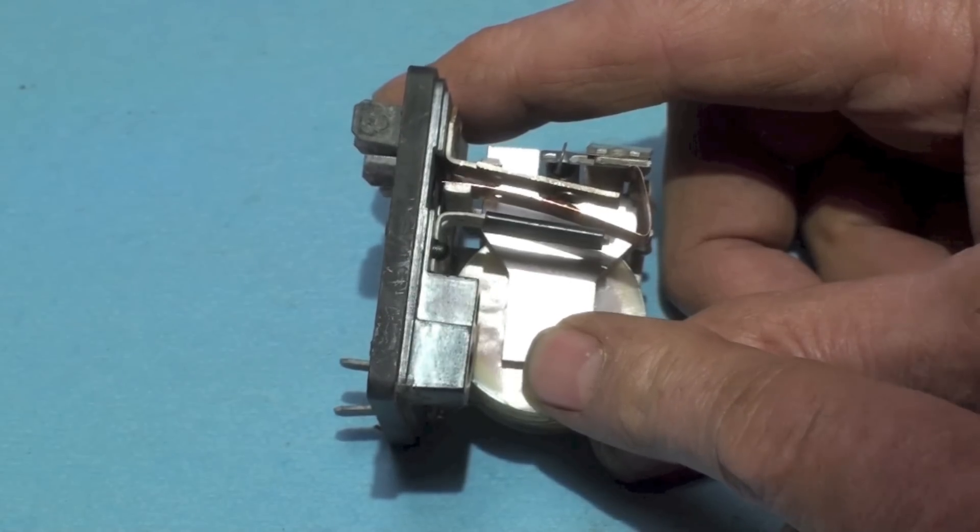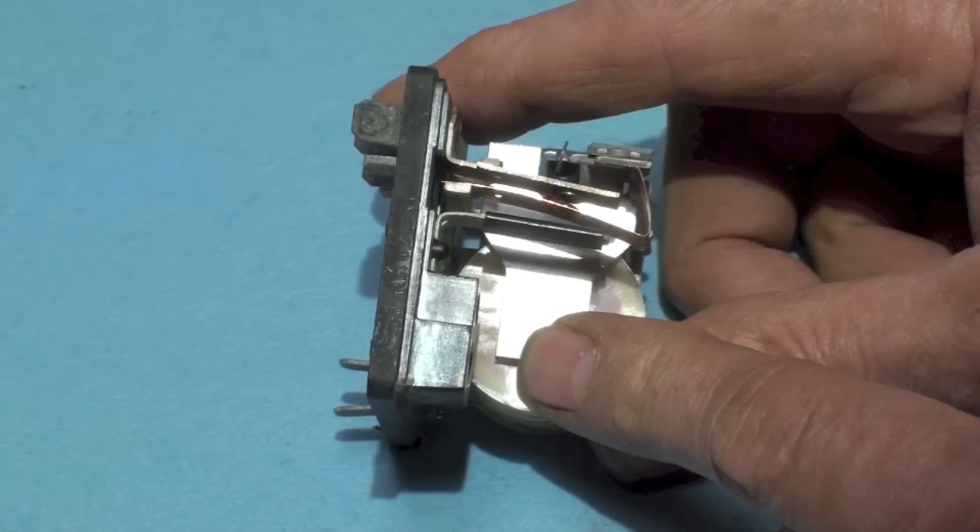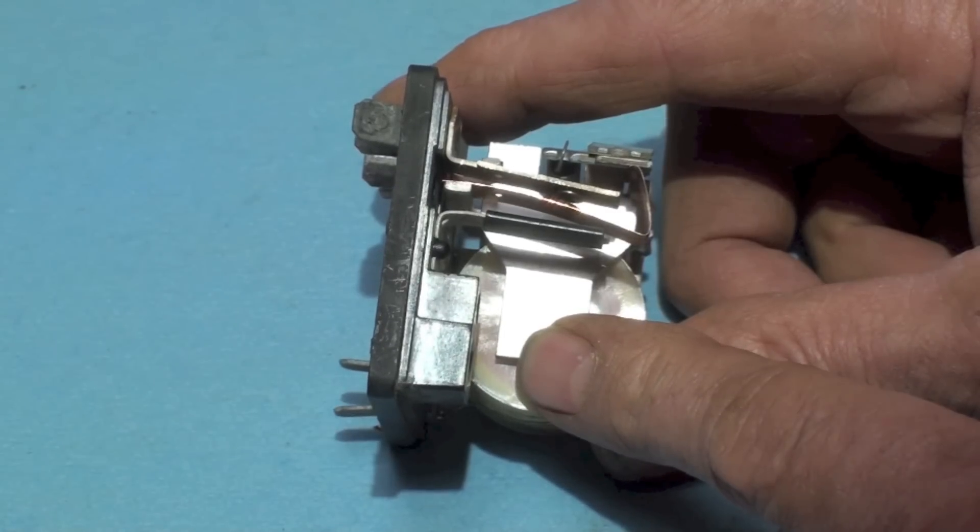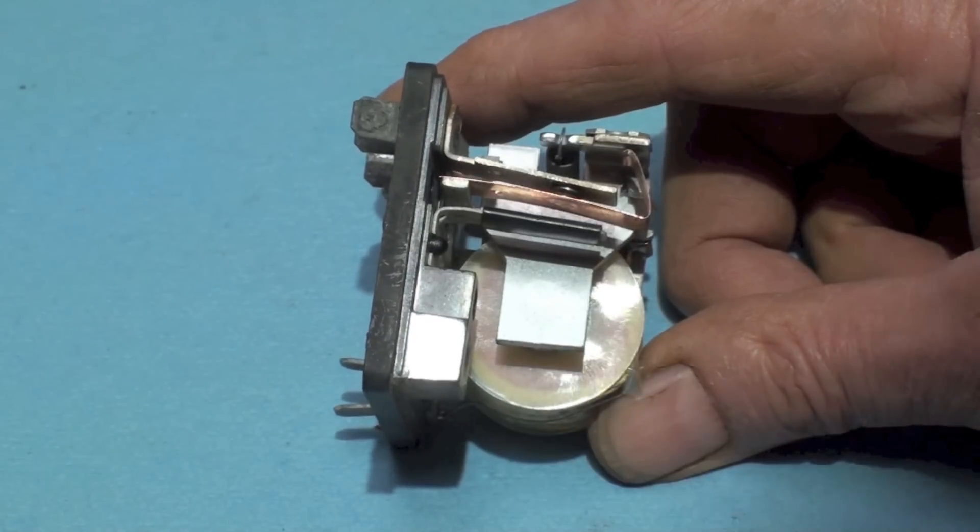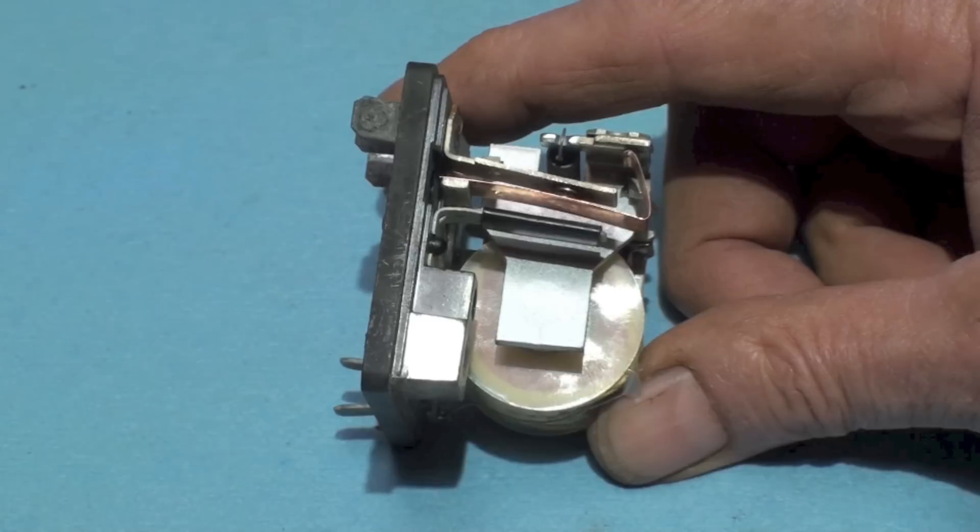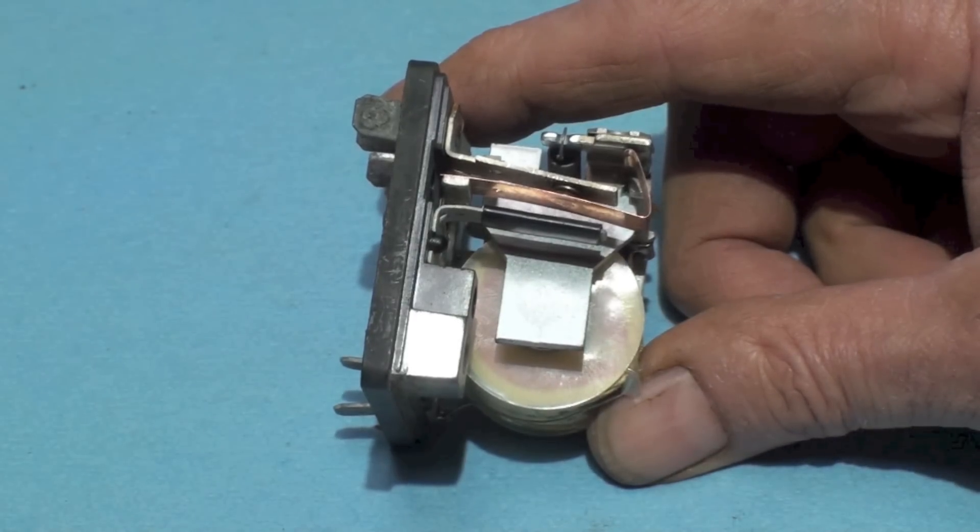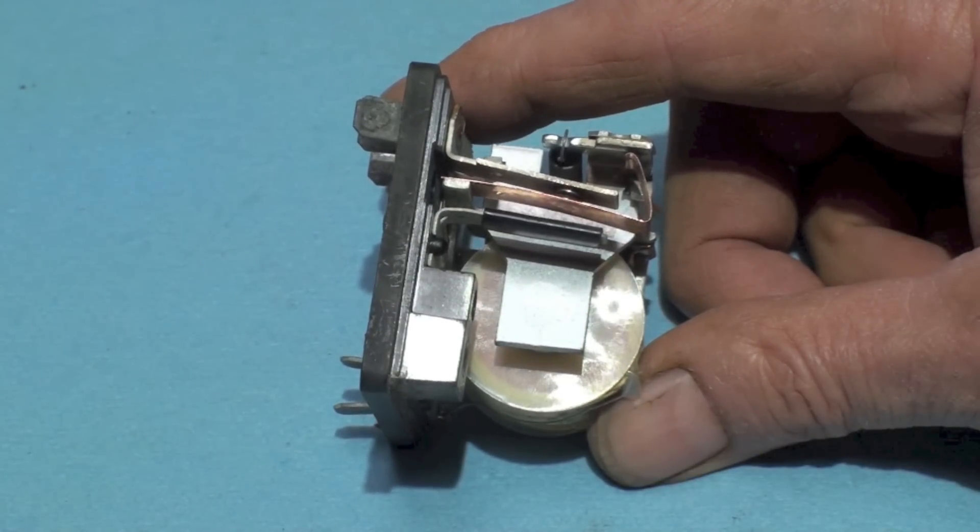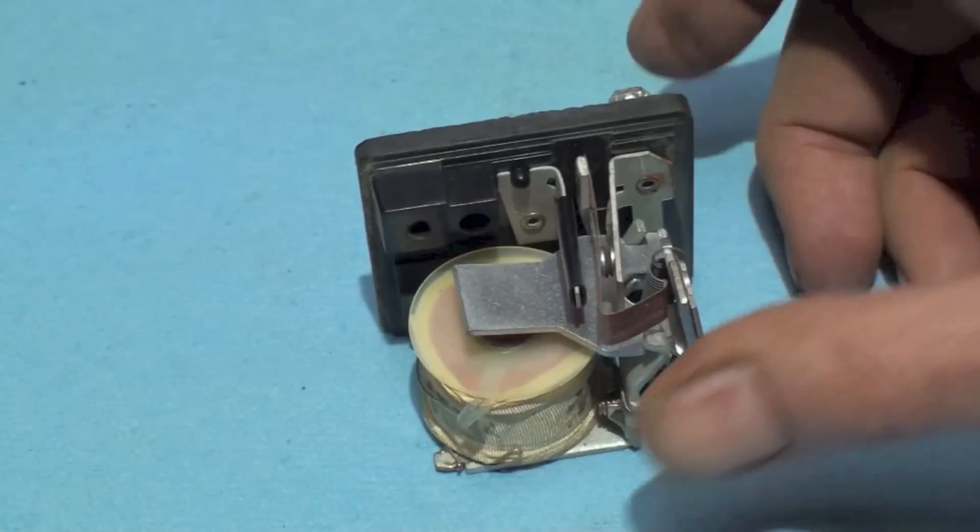And does not get below about 75 percent of its rated speed, in which case if it does, it drops back in again and starts the start circuit up until it reaches that 75 percent. That's all there is to it.